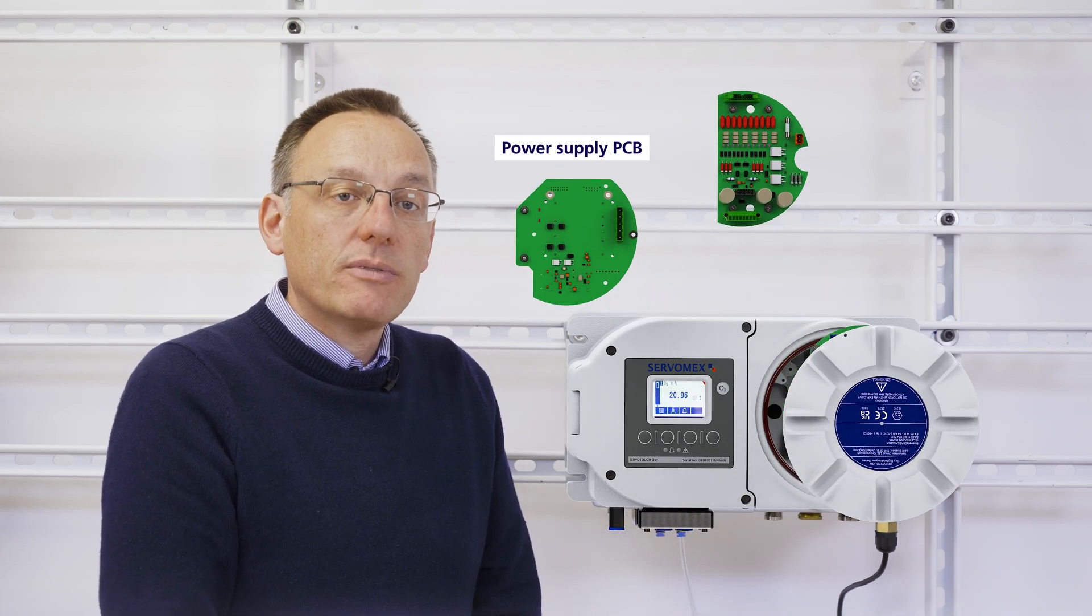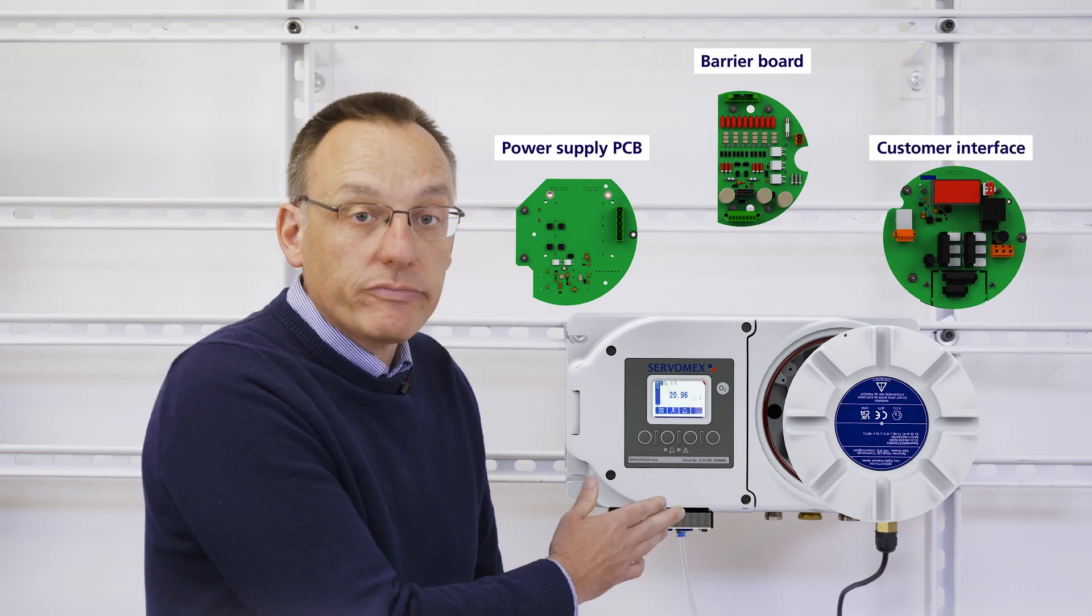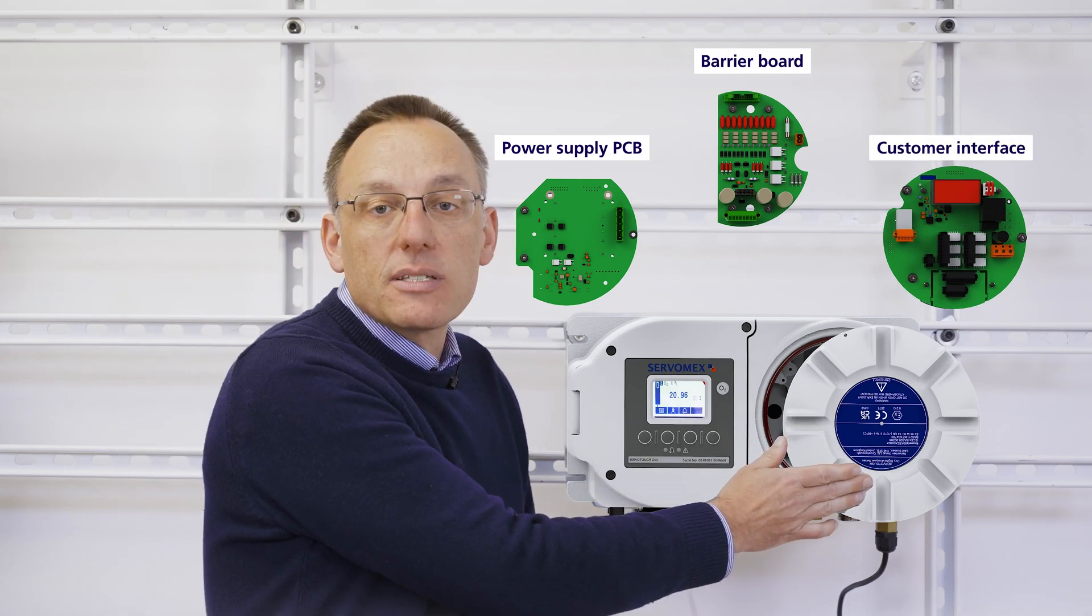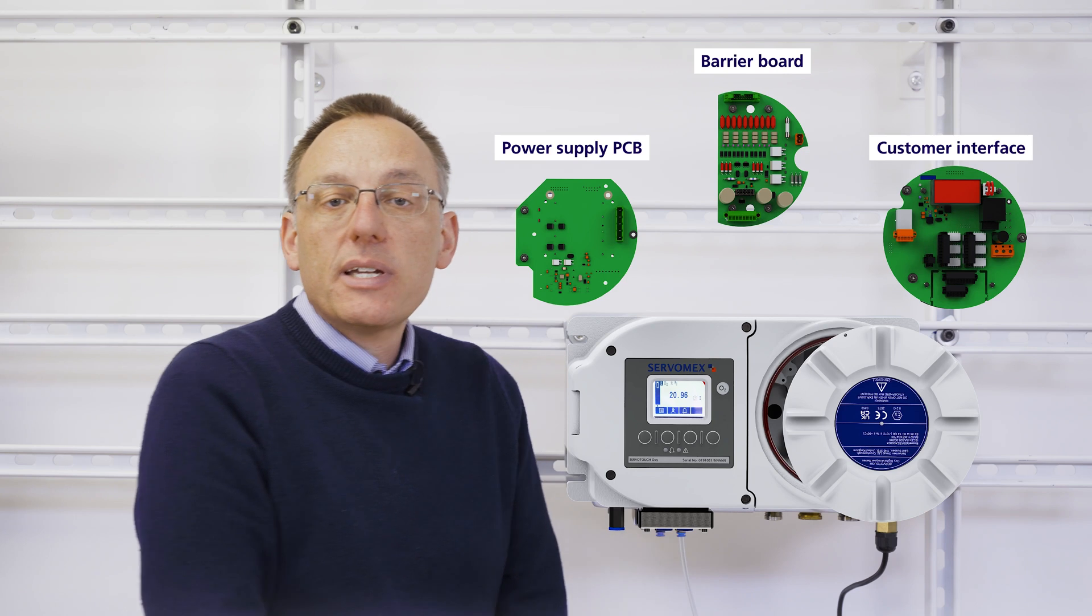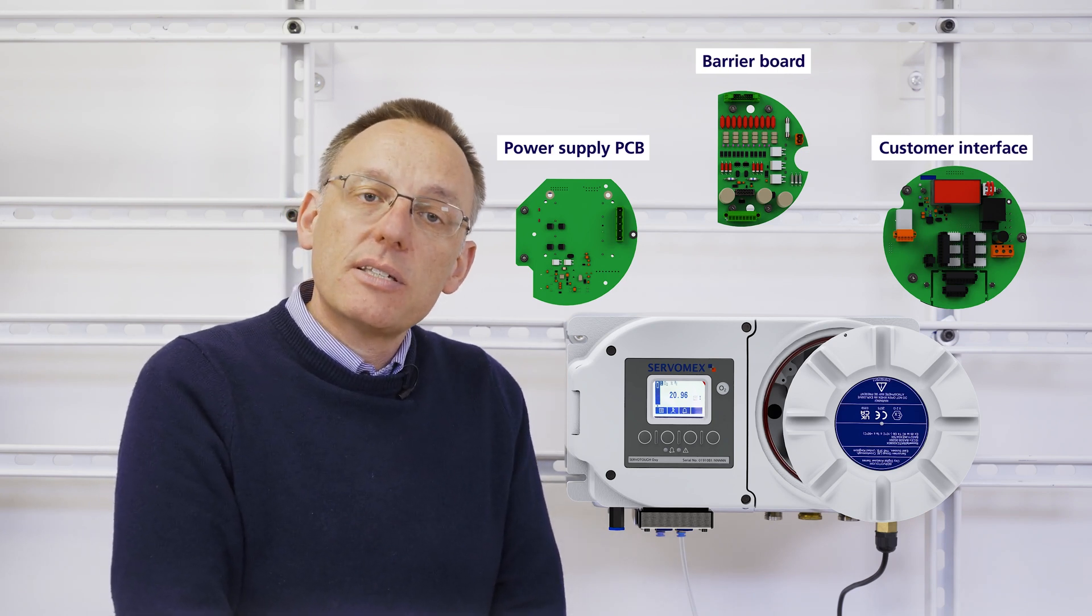The EXD compartment houses the internal power supply and the barrier protection board for the intrinsically safe section and also it houses the customer interface board with connections to interface to the site DCS.